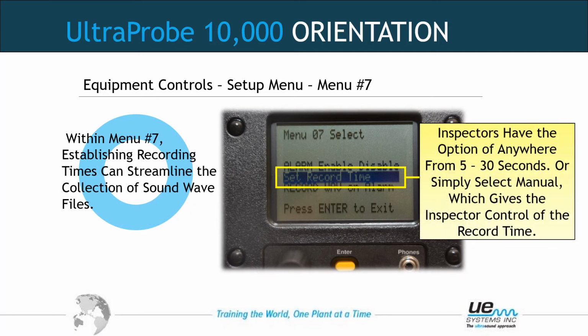Menu number 7, rotating to the right one more time with the sensitivity dial. Set record time. You can preset the recording time of this unit: 5, 10, 15, 20, 25, 30 seconds. The unit will record up to 1 minute in a manual mode. Never less than 15 seconds for a recording. If we're going to analyze, we need at least 15 seconds to build a very good FFT to analyze. Most electrical recordings seem to come in at 30 seconds. Electrical inspectors like to listen to it a little longer, but no less than 15 seconds, whether manual or a preset automatic time. You would select this area by pushing the sensitivity and rotating through the options, and then pressing sensitivity and then enter to exit out.